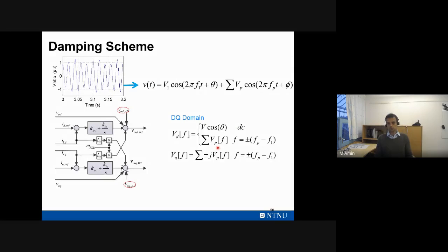The other method for improving stability is using active damping. We have this 15 Hertz oscillation, and we introduce a controller that produces a 180-degree phase shift of this 15 Hertz signal. This additional signal cancels the original oscillation, so that in the system we no longer see the instability.